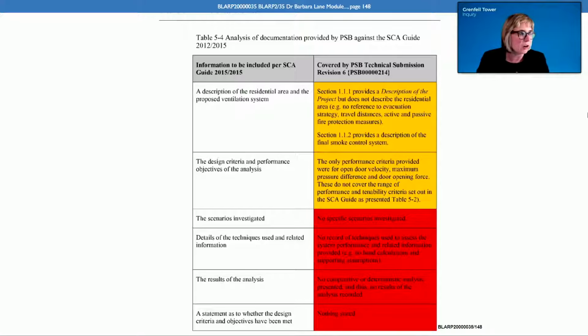Then when it comes to scenarios being investigated, there are no specific scenarios investigated. So it doesn't analyse what would happen if there was an escape of occupants from the fire flat or other flats on that floor. It doesn't indicate what would happen during the firefighting phase. So no scenarios are investigated, no record of the techniques used to assess the system performance, no comparative or deterministic analysis. So what that means is there's no analysis comparing it with a prescriptive system, and no analysis looking at overall performance presented. And there's no statement as to whether the design criteria and objectives have been met. Now, can we agree that was the picture that we now see presented in the design documentation?